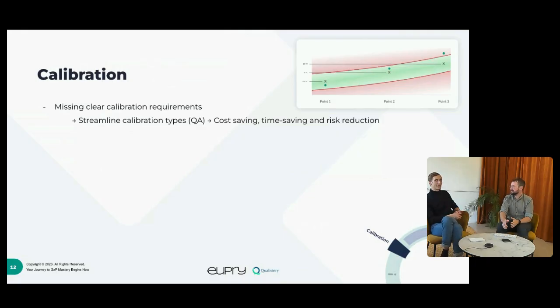And it's a cost-saving thing. Imagine just streamlining something like this that doesn't have any negative quality effect, but it's almost half the price of running our calibration lab with a specific calibration point compared to some predefined points. So it's really something you should consider with your own calibration vendors: there's a big impact on cost saving you can make here. Absolutely, and also because calibration providers will often have a large volume to calibrate, so why not calibrate all of them in the same sitting?